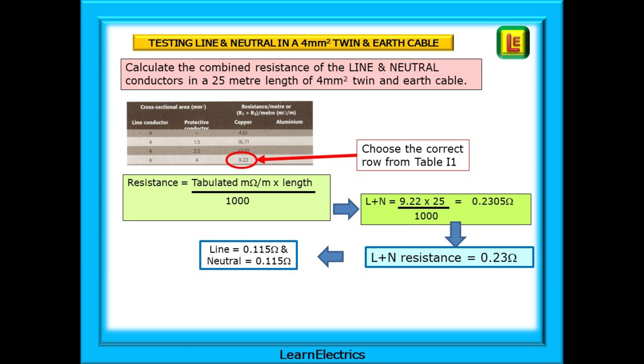And the calculator tells us that this is 0.2305 ohms. We can say, after rounding, that the line plus neutral resistance is 0.23 ohms. We might need to check the resistance of just the line conductor in this radial circuit. Our meter leads will not reach to both ends to measure end to end, so we can link the line and neutral at the one end as shown and then test at the other. As both conductors are the same size, we just halve the answer to find the resistance of the line conductor on its own. If L plus N is 0.23 ohms, then the line is 0.115 ohms on its own.